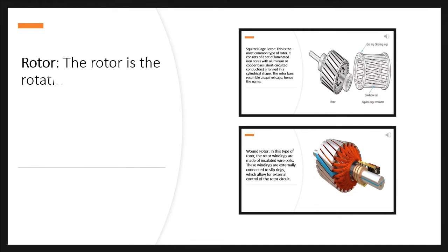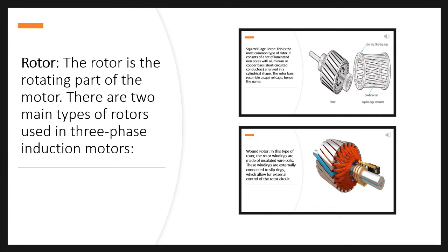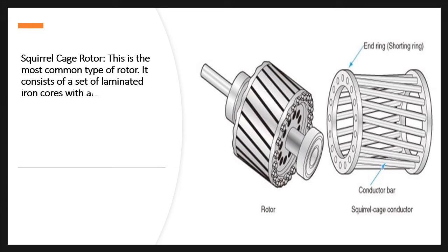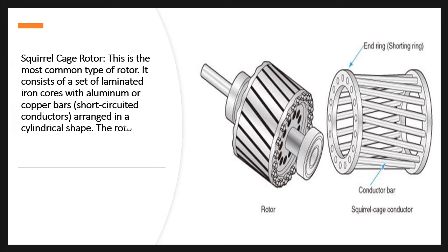Rotor: The rotor is the rotating part of the motor. There are two main types of rotors used in 3-phase induction motors. Squirrel cage rotor: This is the most common type of rotor. It consists of a set of laminated iron cores with aluminum or copper bars, short-circuited conductors, arranged in a cylindrical shape. The rotor bars resemble a squirrel cage, hence the name.